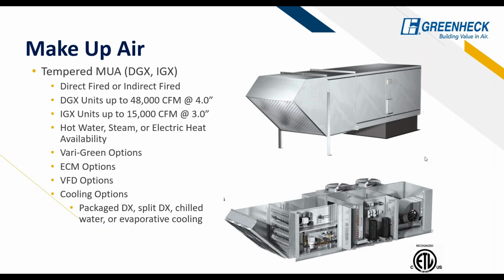We can do cooling options on these as well. I highly recommend doing cooling with kitchens. I don't believe it's required by code, but it might be. I see a question coming in: is AC required by energy code? When I now read it, it appears so. That might be so. That would be news to me, to be honest. I will look into that right after this, and I'll follow up with you, Daniel, on that one. But as far as I know, it wasn't required. And typically I would always require it because I do get a lot of complaints in the summer months that makeup air is not tempered with cooling.